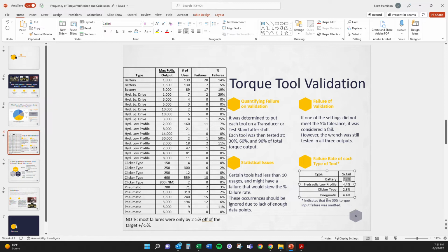The hydraulic low profile had a failure rate of 4.4. There's not a lot of data points there, so that's kind of higher than what we would expect, right? And the pneumatics, it was the same thing. We were using them on the low end. So what we found is that you're probably going to expect a 3 to 5% failure rate of the plus or minus 5% tolerance that most manufacturers say.